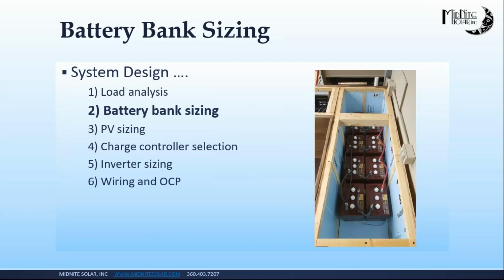And if it's warmer, you might charge it to 14.5, which is the same as 14.8, because the batteries are warmer. You don't have to hit it with as much voltage. So T-comp is very, very important to maintaining your batteries, setting that up correctly.